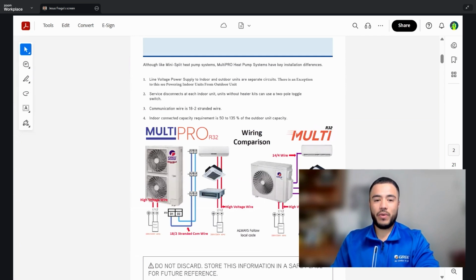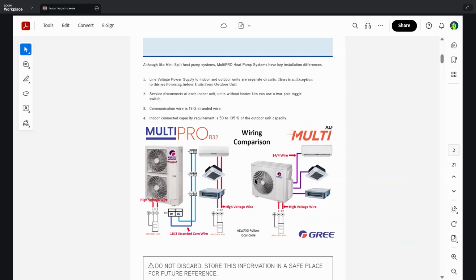So in MultiPro R32, we know that we have a communication data chain that goes to the indoor units. We still have our line voltage power. And to compare that to multi-zone mini splits, we know that multi-zone mini splits is 14/4 communication wire and power. So that means that this wire here has four conductors. One's used for communication, the other is used for ground, and the other two are for power.